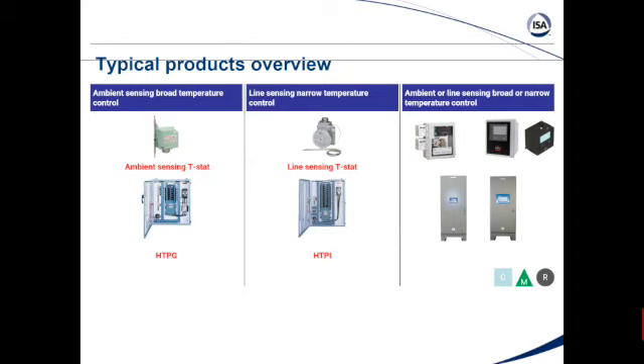It can be terminated easily. That's what I'm always driving towards. So when there's an MI cable application, it's not because of preference, it's because of necessity. And that necessity is typically either you have a really high maintained temperature that we can't maintain with a plastic product, or you have a process that has a very high exposure temperature that would damage our cable. When either one of those situations or both of those are met, then we go to an MI cable option.